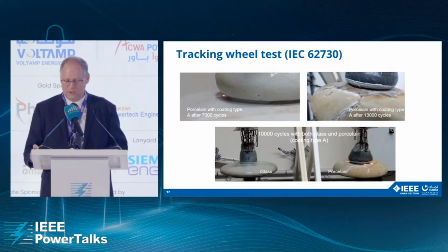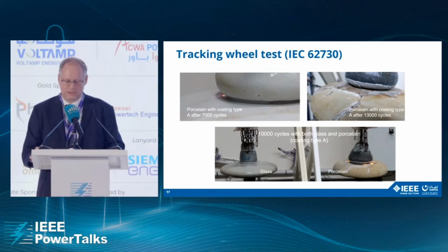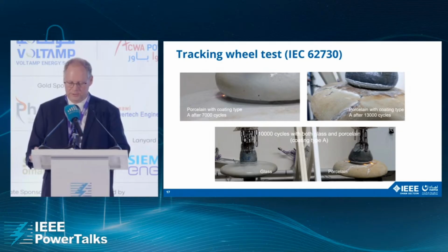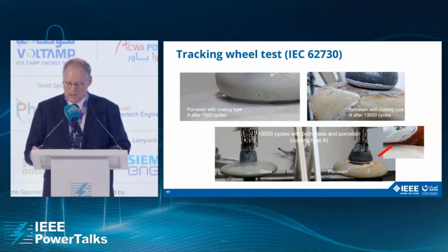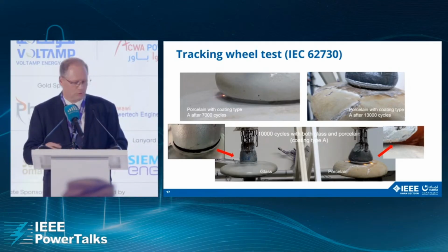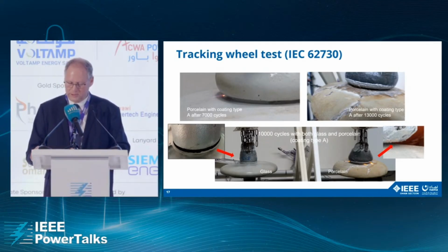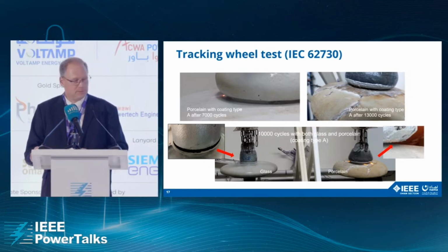The development of dry band arcing over time intensifies as the hydrophobicity is being lost or reduced. The behavior on the top surface of the insulator is strongly influenced by the assembly of the cap on the dielectric surface. A gap between the base of the cap and the upper surface of the porcelain insulator will promote discharge activity, leading progressively to severe erosion, whatever the type of silicone. This phenomenon is less prone to occur when the cap is sealed on the glass disc as per Sediver design.